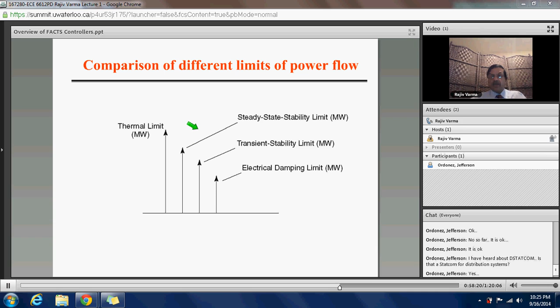Okay, so what do the FACTS devices do? The FACTS devices do many things. First of all, they increase the power transmission capacity in a line. So if, for example, the transient stability limit is here, the FACTS devices can raise this arrow from here up to the thermal limit. This is what the FACTS devices can do if they are installed in a transmission line properly.